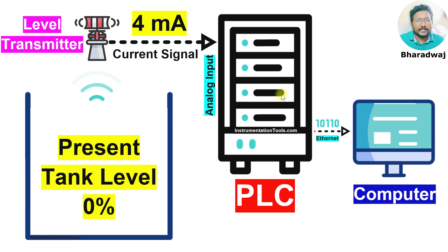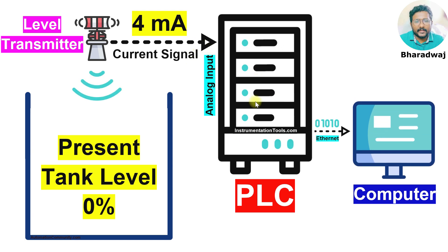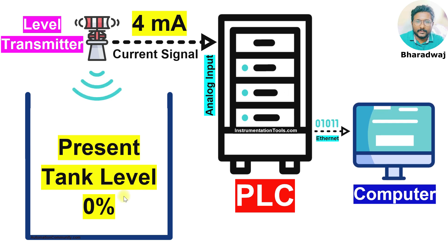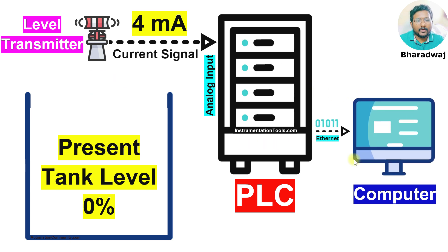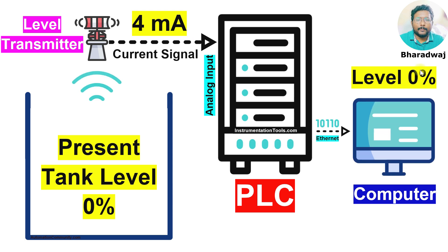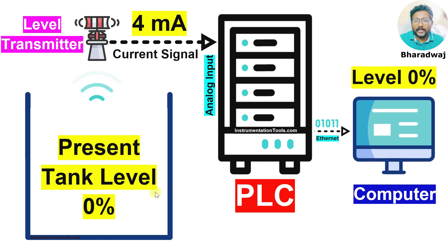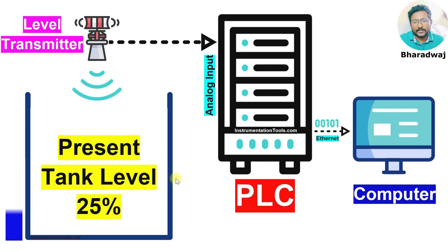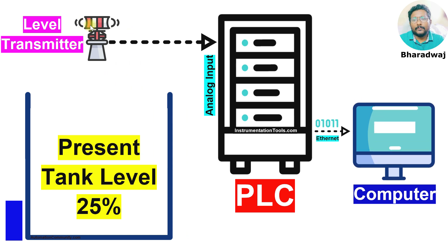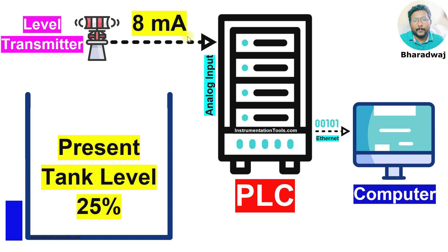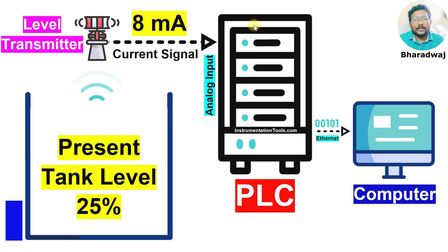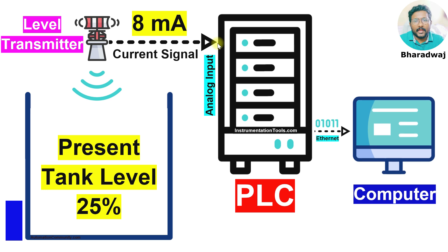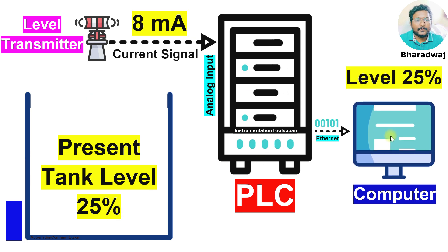The PLC receives the 4 mA signal and calculates the tank level. Finally, it updates the tank level on the computer graphics — the level is 0%. Now if the tank level is 25%, the transmitter sends 8 mA to the PLC. The PLC receives this current signal, calculates the tank level as 25%, and displays it on the computer.